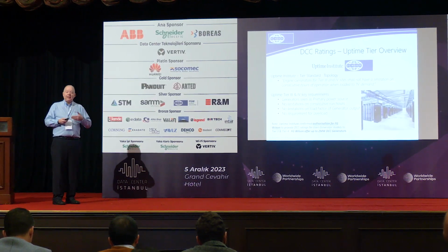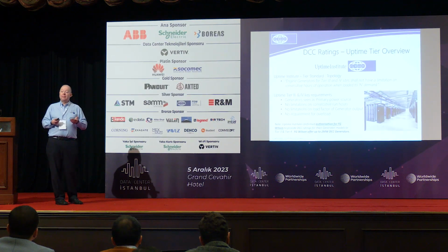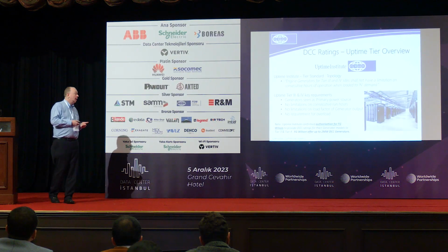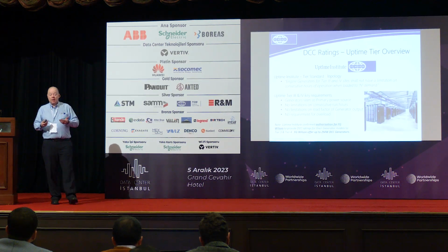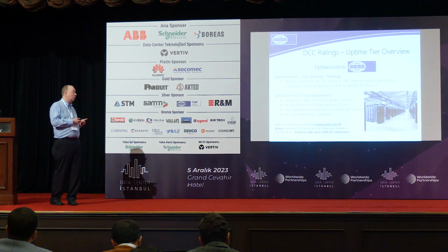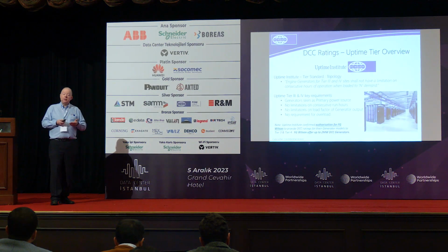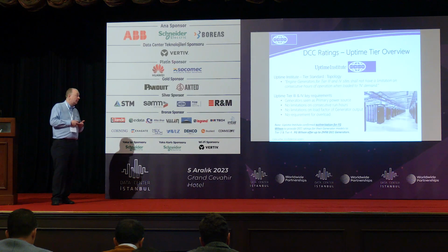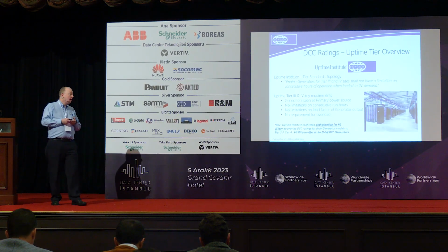And in fact, it sounds a bit strange, but they actually see the genset as the primary source of power. They also have no limitations on runtime, and you can be up to 100% load factor.